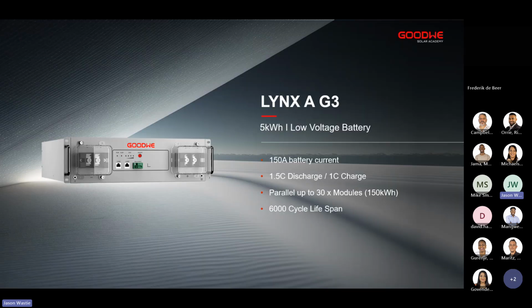So if we just have a quick look at our Lynx AG3 battery, it is a 5 kilowatt hour low voltage battery, with a 150 amp battery current. It's a 1.5C discharge and 1C charge battery that can parallel up to 30 modules, 150 kilowatt hours, with a 6,000 cycle lifespan. The Lynx AG1 battery is our 0.5C battery.